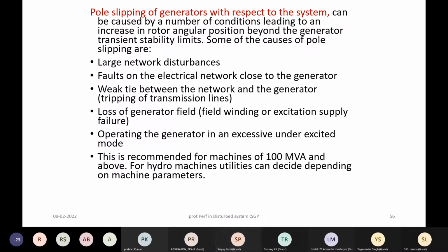So in many hydro generating stations, you may not have pole slip protection. For all thermal machines of say 250 megawatt and above, pole slip protection is mandated. For hydro machines of 100 megawatt and above, again it is now mandated. But the risk to a hydropower station on account of pole slip is much less, because the chances of severe unstable power swing experienced by the hydro generator, because of its moment of inertia and mass, are much lesser compared to the thermal power station. So many of your stations are perhaps without pole slip protection.